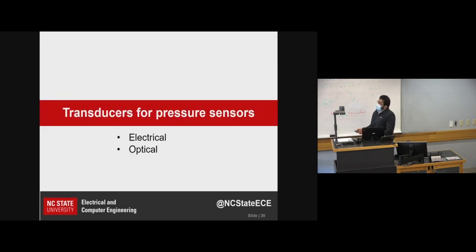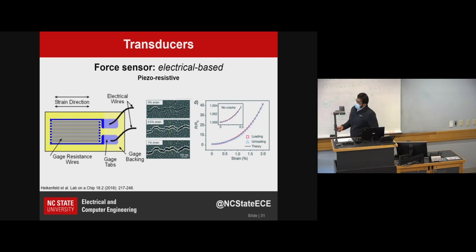Okay, now let's move on to transducers for pressure sensors. Again, we will discuss electrical and optical. Let's take the case of electrical. So here I show a piezoresistive. Piezo means pressure, force. Resistive. So as you apply the force, the resistance changes.